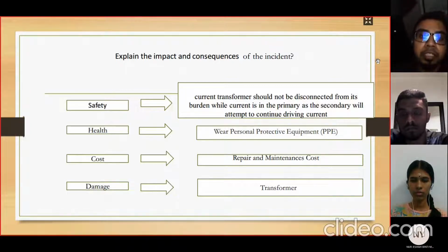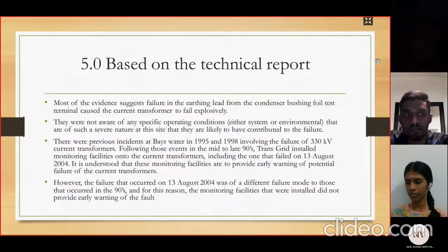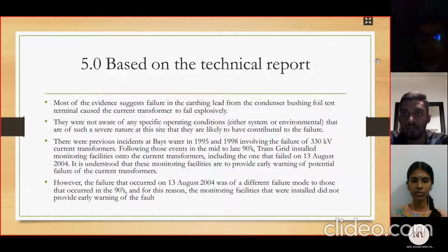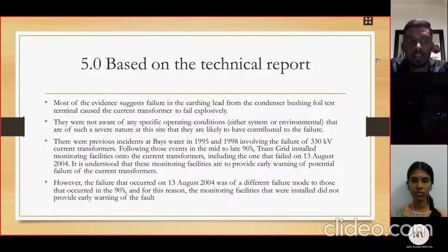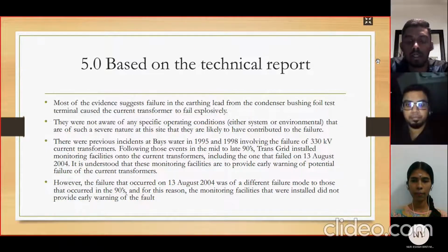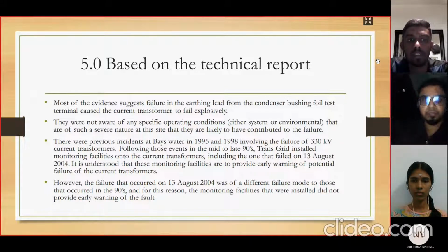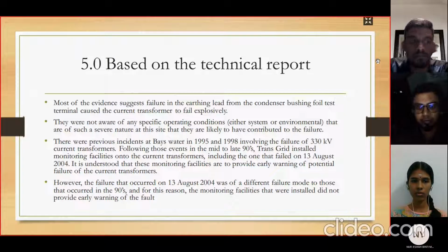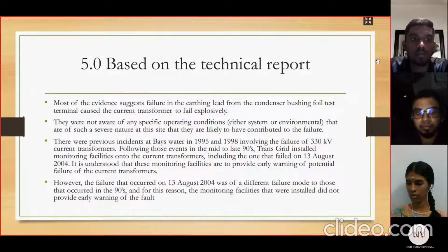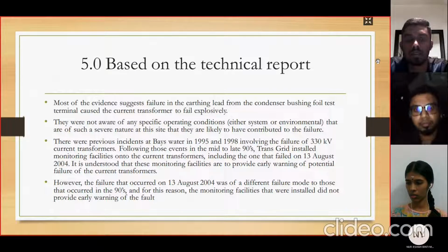Next slide, Ikram will present it. Based on the technical report, what I have understood is that most of the evidence suggests failure in the earthing lead from the condenser bushing foil test terminal caused the current transformer to fail explosively. They were not aware of any specific operating conditions, either system or environmental, of such a severe nature at this site that are likely to have contributed to the failure.